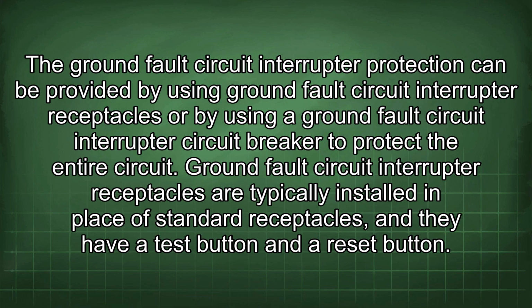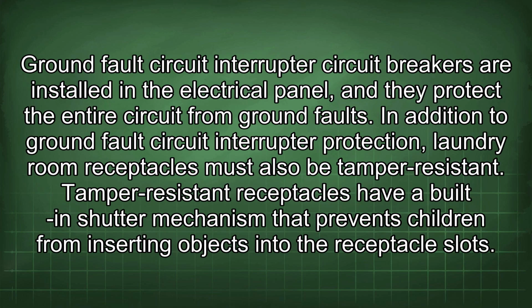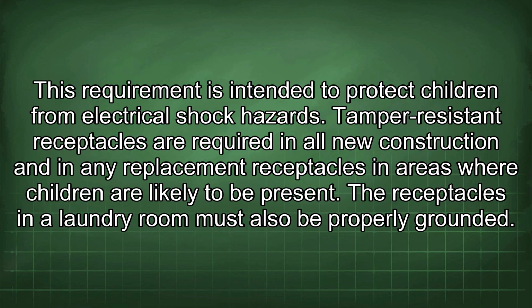Ground fault circuit interrupter receptacles are typically installed in place of standard receptacles, and they have a test button and a reset button. Ground fault circuit interrupter circuit breakers are installed in the electrical panel, and they protect the entire circuit from ground faults. In addition to ground fault circuit interrupter protection, laundry room receptacles must also be tamper-resistant. Tamper-resistant receptacles have a built-in shutter mechanism that prevents children from inserting objects into the receptacle slots. This requirement is intended to protect children from electrical shock hazards.